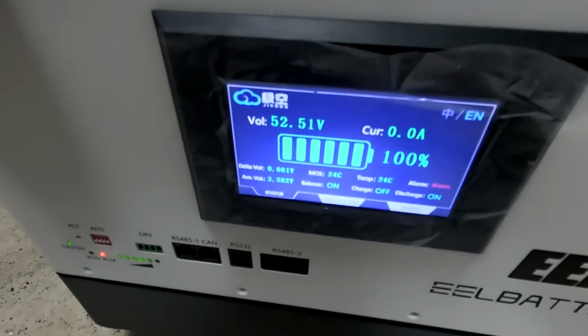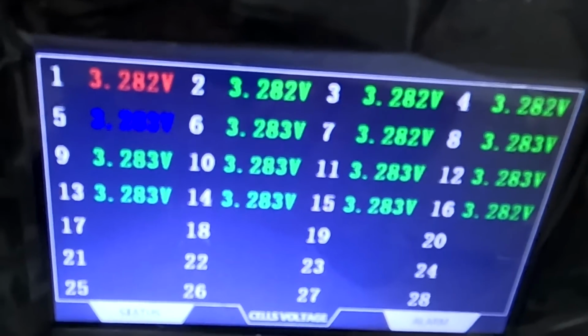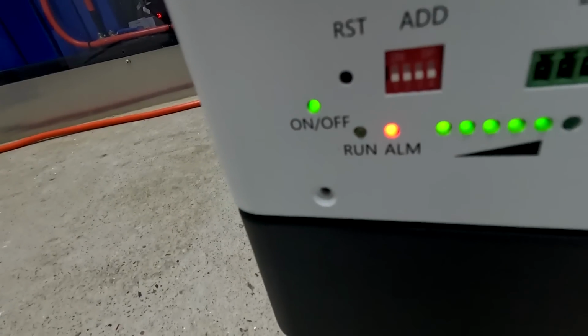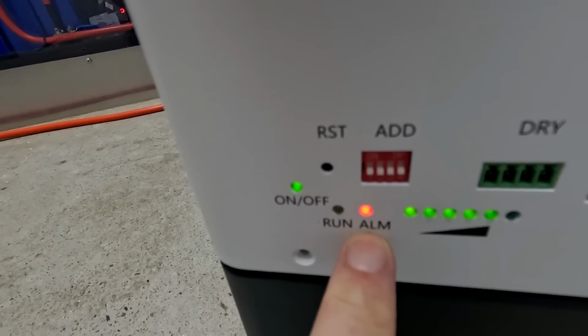Now, the battery is clearly not at 100% state of charge. 3.28 looks fairly balanced, but this doesn't mean anything because we are not fully charged, so you cannot compare battery voltages or cell voltages at all if you're not above 3.45 volts. Oh shit, we've got an alarm.